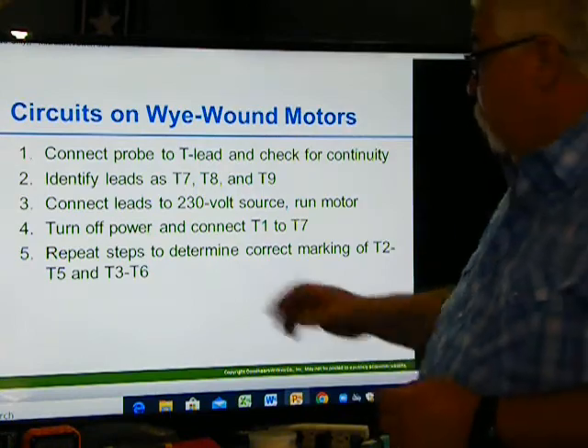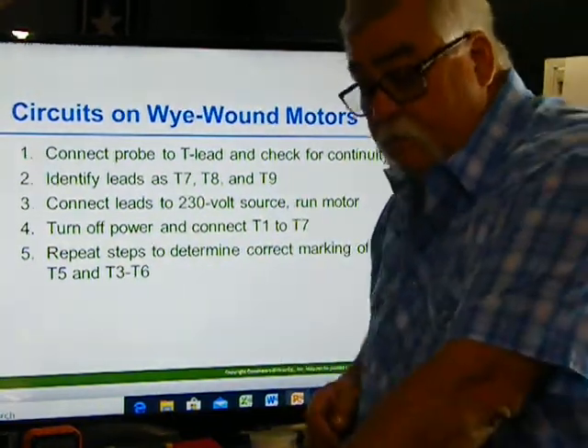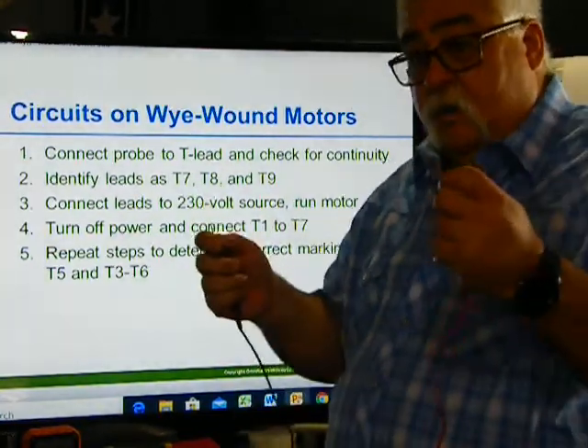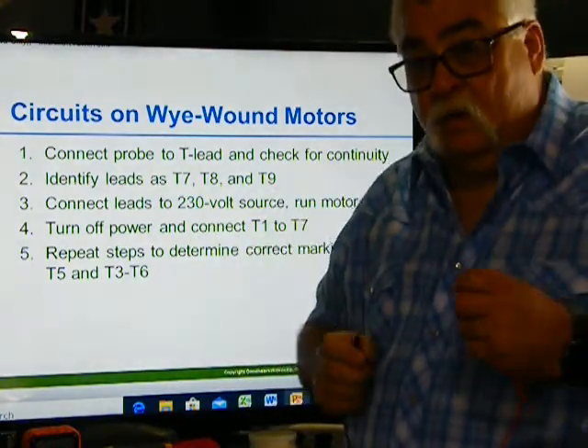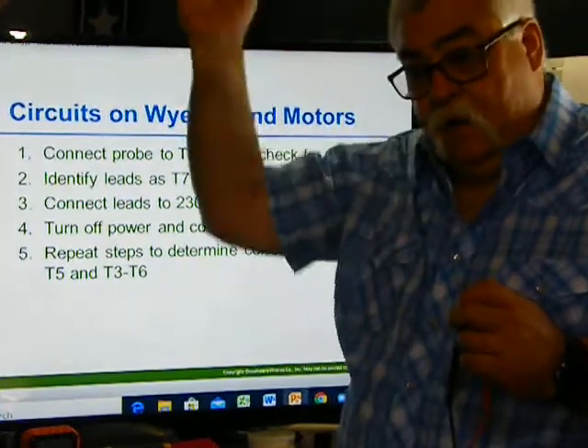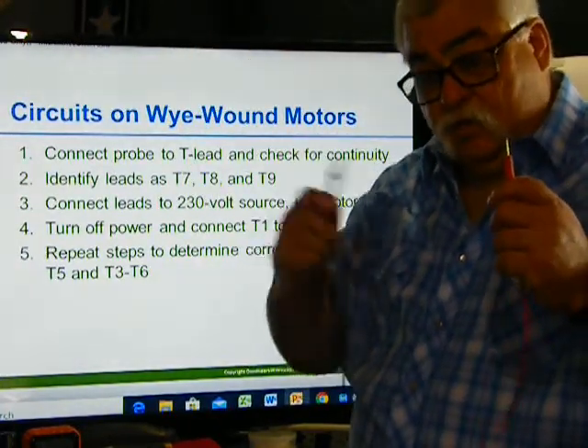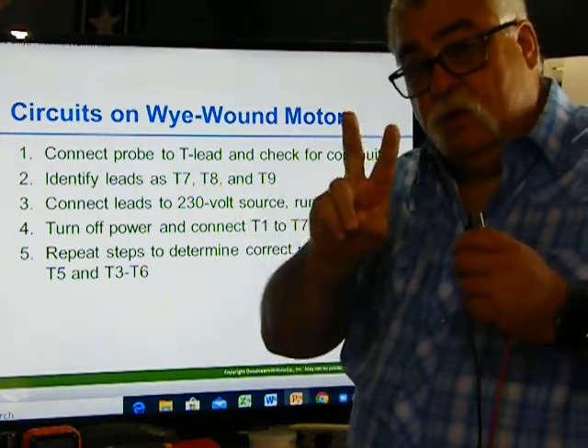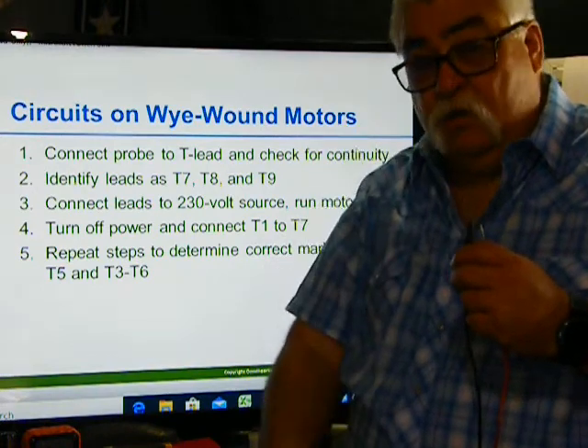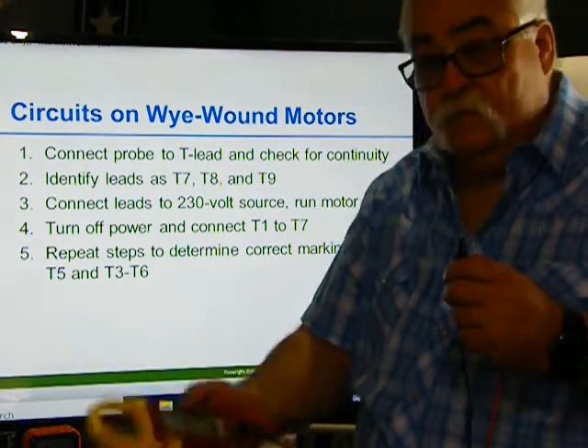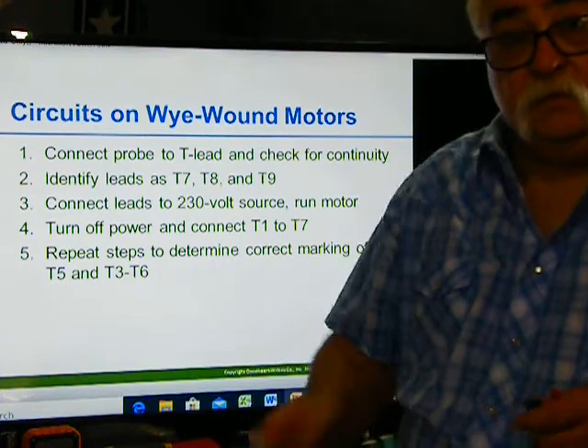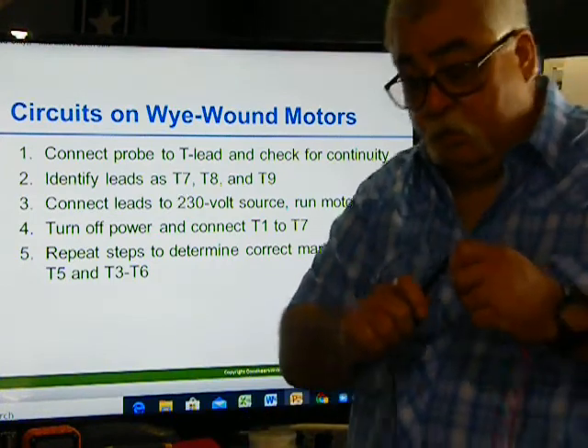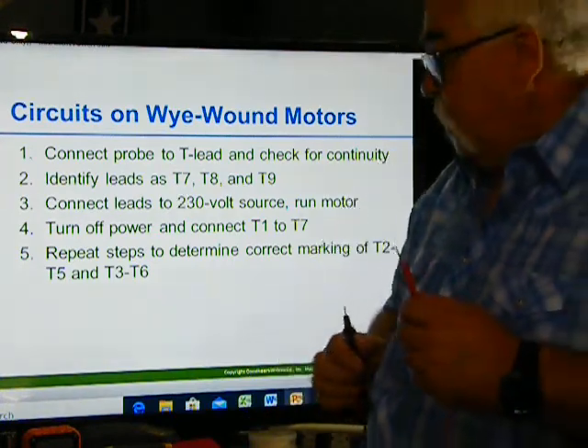If you grab one wire and put your lead on it, and you go to another wire, and it gives you a good reading instead of an open line or a high resistance number, then you're reading across the windings. When you get one and the number comes down, it means those 2 windings are tied together. So you can check it with an ohm meter. All you have to do is put it on ohms, or put it on the bell. If it's a contact, it's going to make a noise.